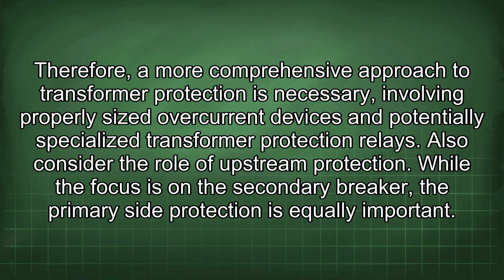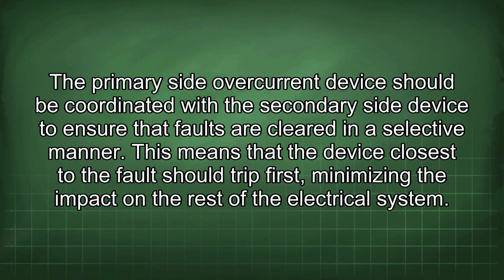Also consider the role of upstream protection. While the focus is on the secondary breaker, the primary side protection is equally important. The primary side overcurrent device should be coordinated with the secondary side device to ensure that faults are cleared in a selective manner. This means that the device closest to the fault should trip first, minimizing the impact on the rest of the electrical system.